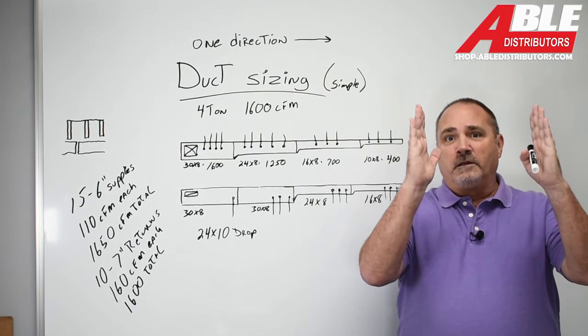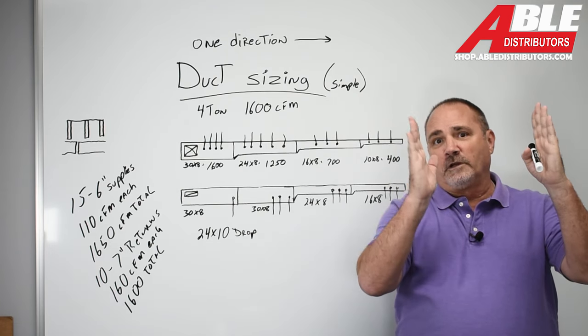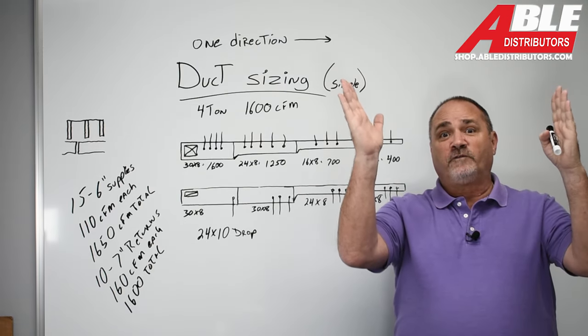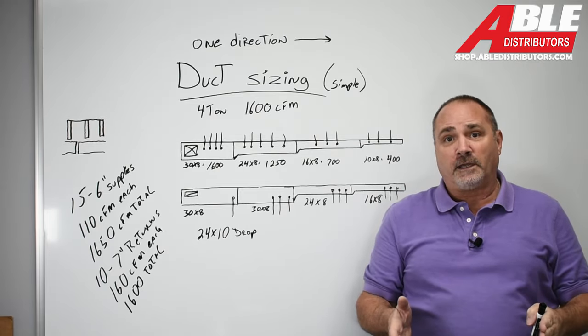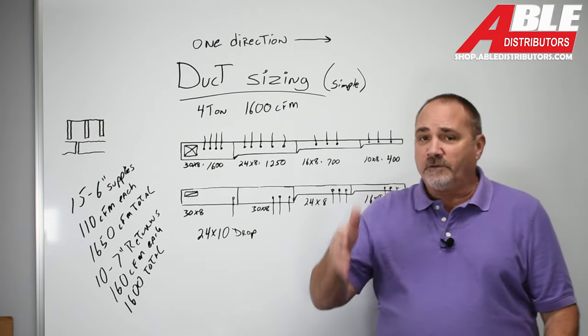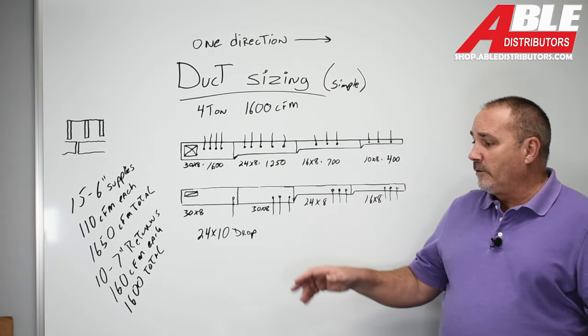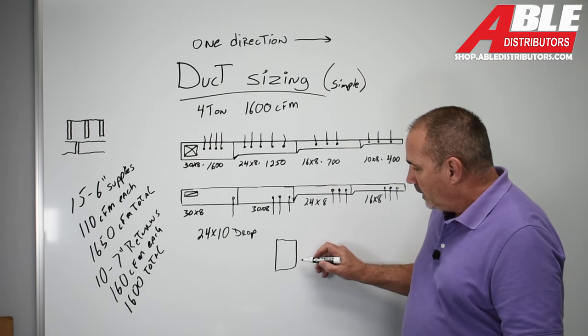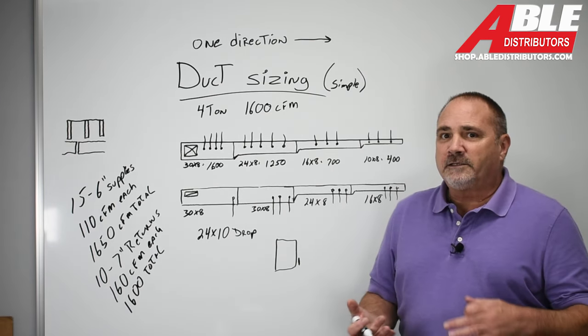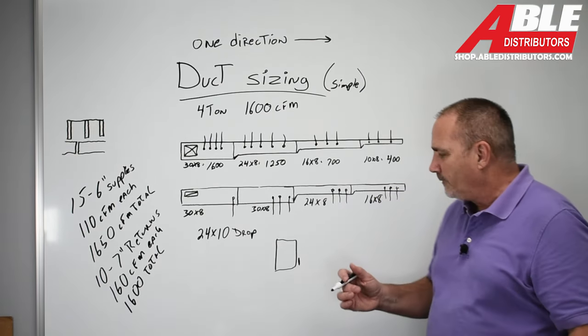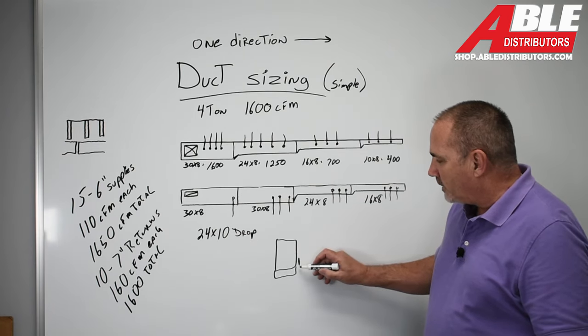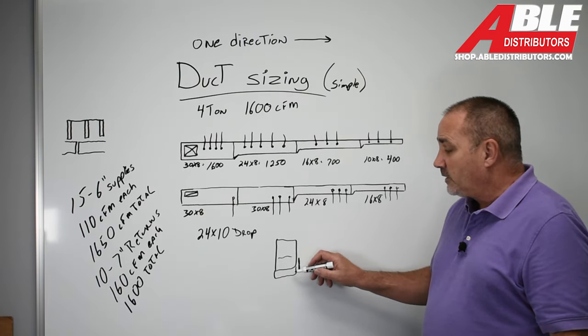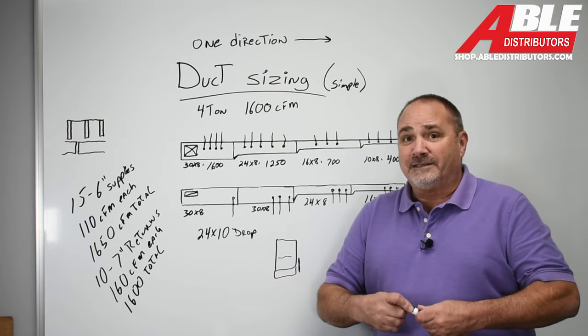Now, if it was me, when I take that drop into the ductwork, I'm going to build my own little transition. So my opening at the ductwork, it might be 24 by 15. I'm going to build a little transition to get down to 24 by 10. Drop all the way down. Put a filter. If you can't do an elbow, just come all the way down. Put it on a box. Put the furnace on the box, because that furnace, if you just take and cut an opening inside, the max opening you're going to get is about 14 inches. If you put it up on a six-inch box, now you can get a full 20 inches. Taking some off the side of the furnace, some off the bottom, take out the bottom of the furnace. It'll definitely help.